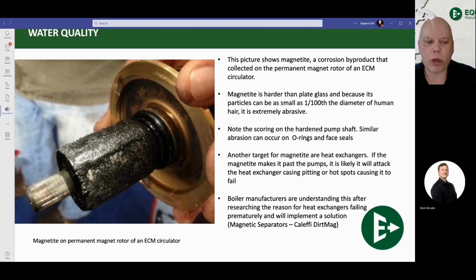The worst color hydronic water that you can see is going to be black. When we see black, we know that's going to be the incorporation of magnetite. I want you to think of magnetite essentially as like a liquid metal. It is an extremely fine particle of ferrous metals, so it's going to be magnetic or stick to a magnet, and it's going to stick to any hot surface inside of a hydronic system. The hottest surface inside of a hydronic system is going to be the heat exchanger for the boiler, and your magnetic portion is going to be in your pumps. So it'll stick to your heat exchangers and it'll stick to your pumps.